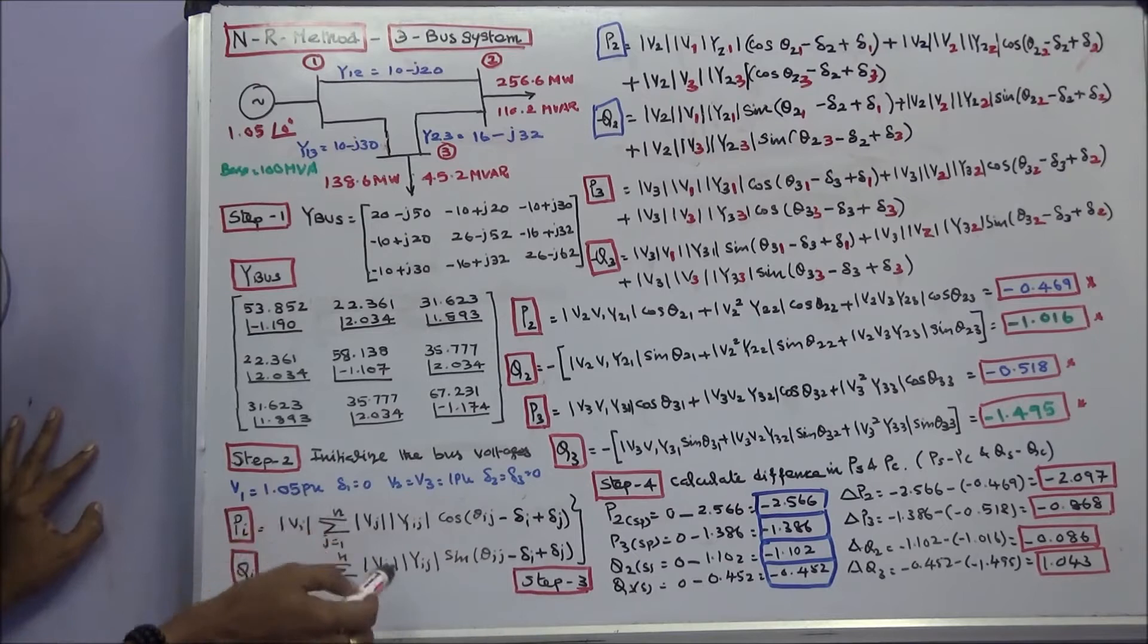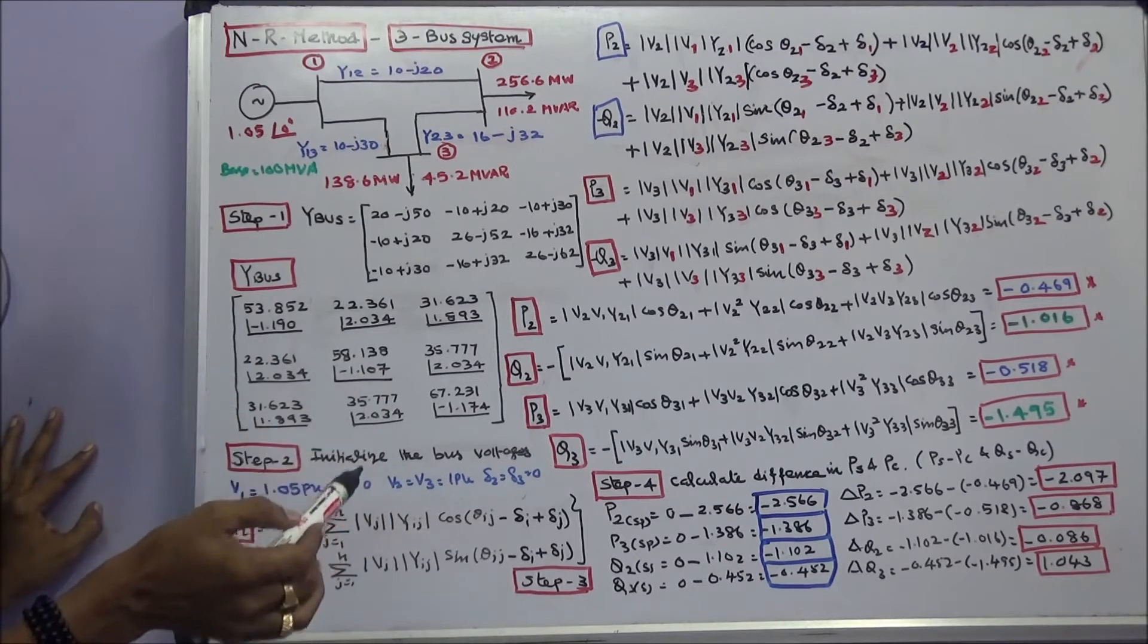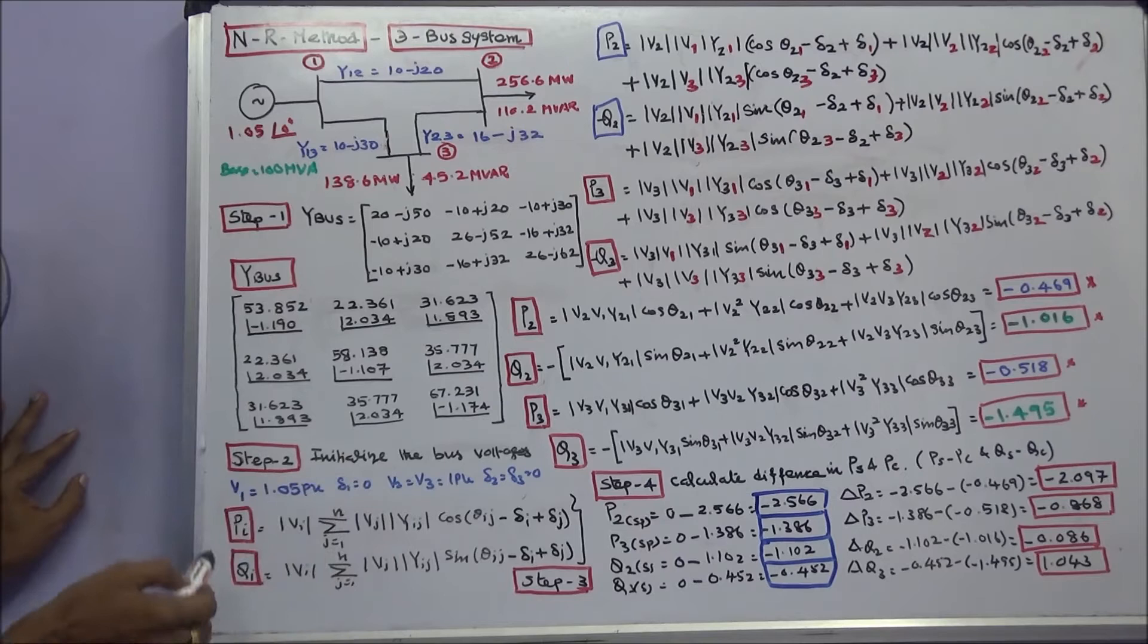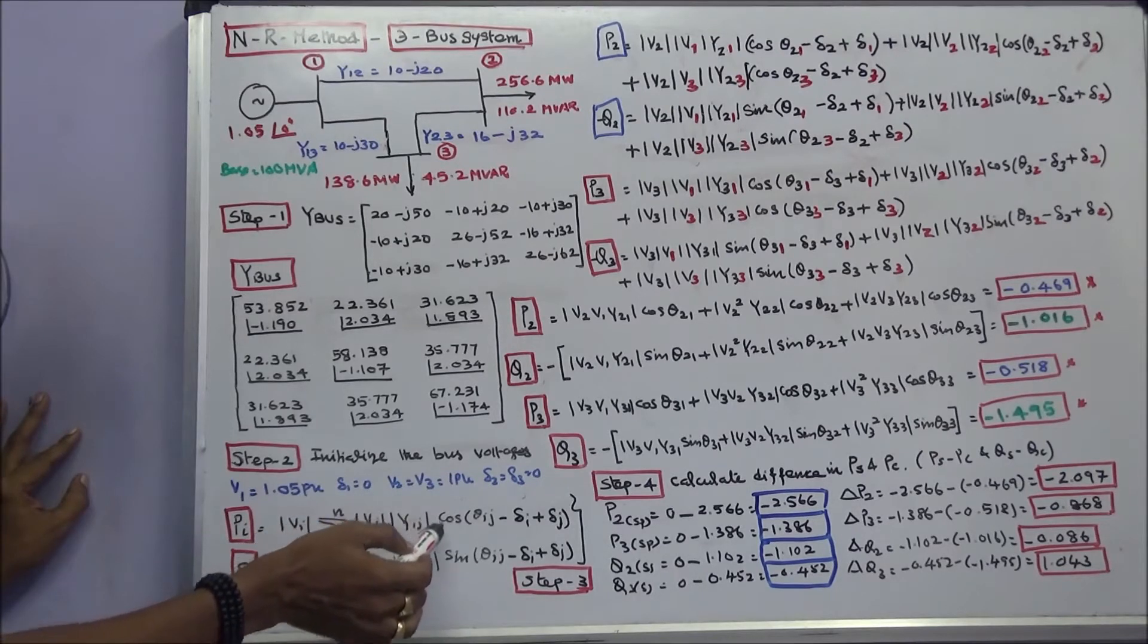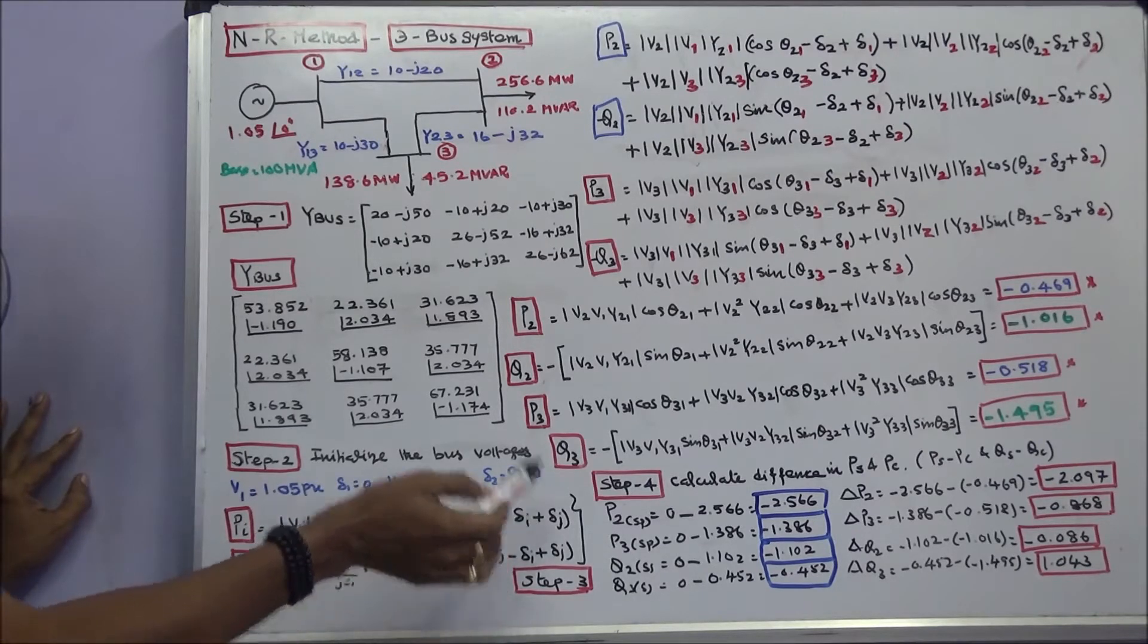Third step we have to find the P2, Q2, P3 and Q3. The general formula is PI is equal to modulus of VI, sigma J is equal to 1 to N, modulus of VJ, YIJ, cos theta IJ minus delta I plus delta J.